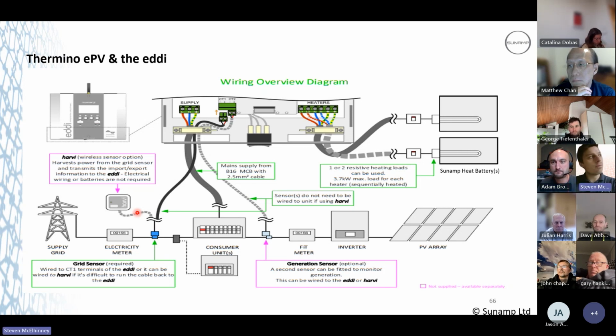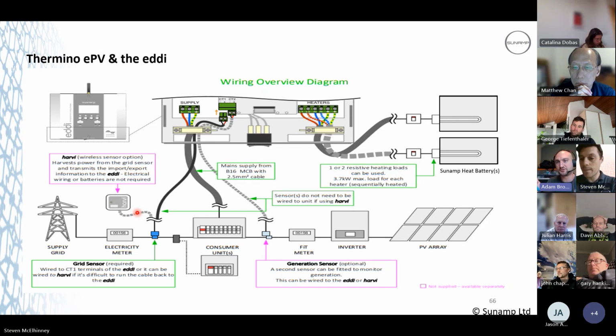Yeah. So with that, you probably want to have a time boost set in the morning between, I don't know, 3 and 6, for 3 hours. And then that means the customer's going to have hot water. Obviously, you set the time boost around the customer's schedule. Of course, yeah, but it wants to be ready for the demand, doesn't it? Prior to the demand. That's exactly it. But 3 hours is the rough timer just to keep it. I mean, it should take about 2.5 hours for a 150 fully charged, but you can set for 3 hours, and the unit might only be charging for an hour and a half or 2 hours, with that live flow of electricity.